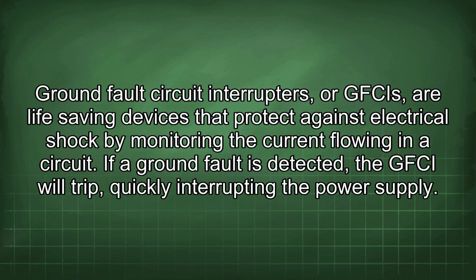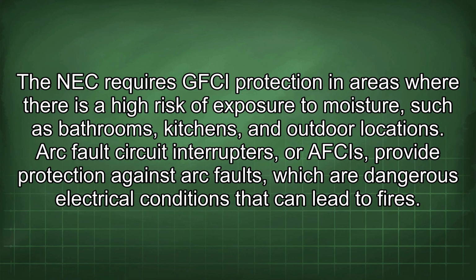Ground fault circuit interrupters, or GFCIs, are life-saving devices that protect against electrical shock by monitoring the current flowing in a circuit. If a ground fault is detected, the GFCI will trip quickly, interrupting the power supply. The NEC requires GFCI protection in areas where there is a high risk of exposure to moisture, such as bathrooms, kitchens, and outdoor locations. Arc fault circuit interrupters, or AFCIs, provide protection against arc faults, which are dangerous electrical conditions that can lead to fires.